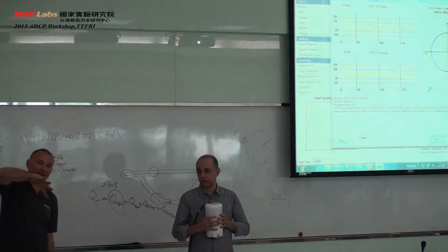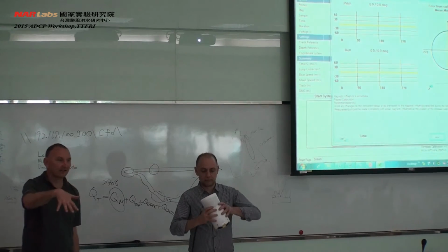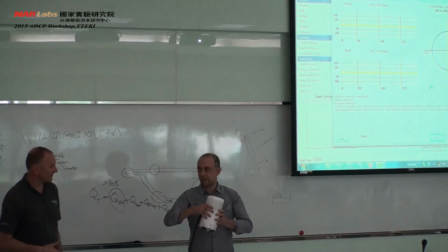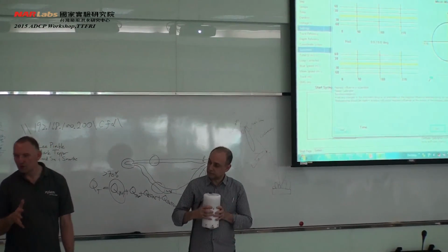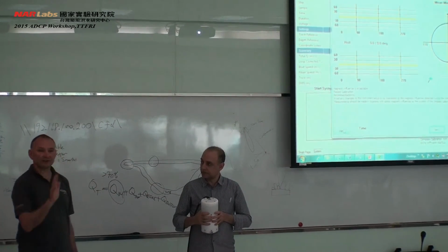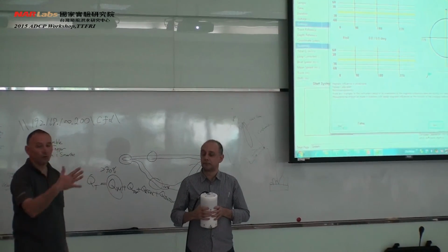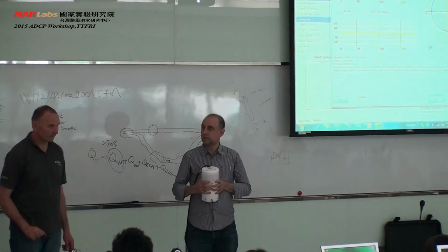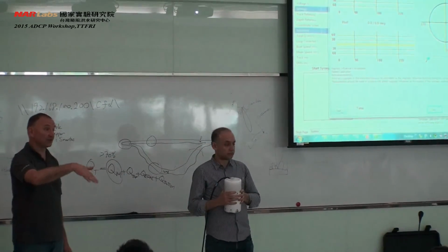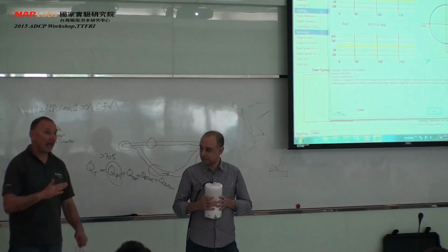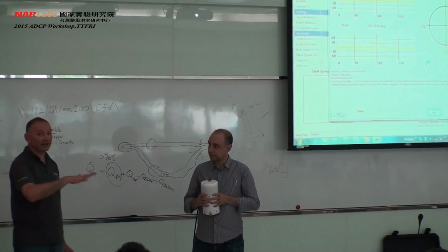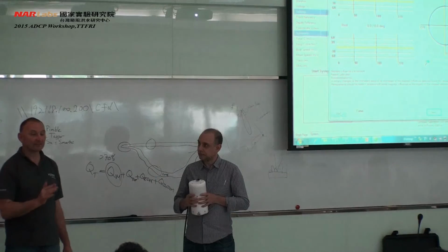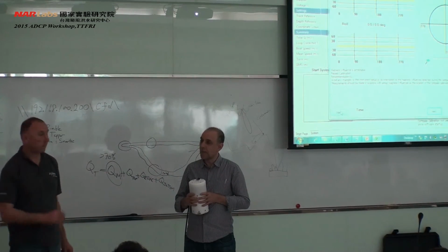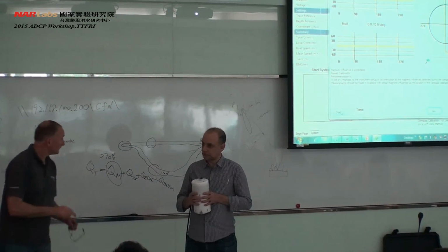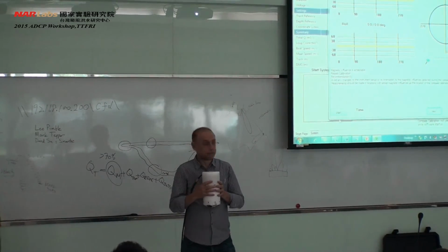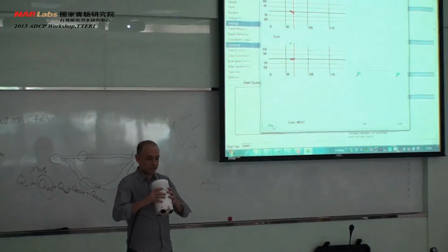We should also make the pitch and roll on the compass as we're doing that. And that pitch and roll should be to the amount that the instrument is going to pitch or roll in the channel. If we don't do it sufficiently, if the instrument pitches or rolls greater than our calibration, then that data might be compromised out in the field. So, Mark, off you go.